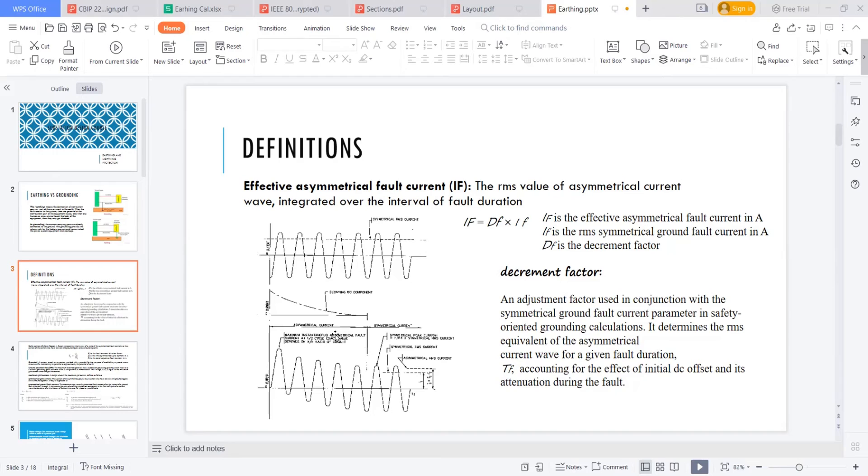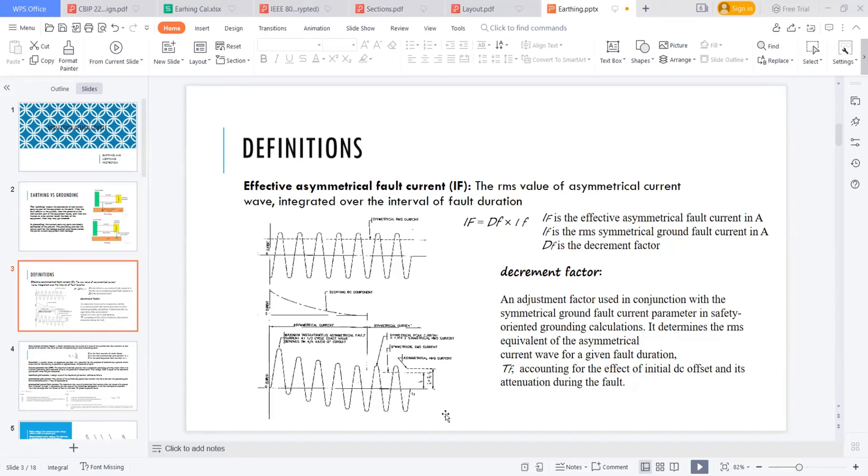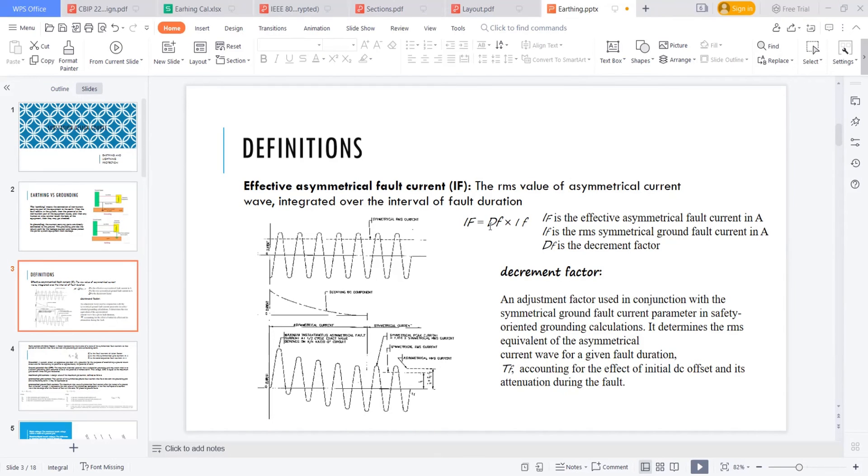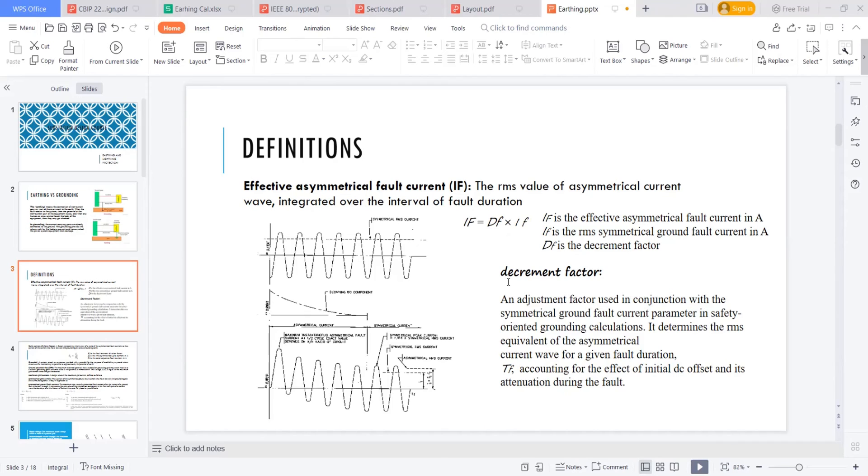This is the asymmetrical fault current. And after the decaying of this DC component, the fault current will come to its normal position where this symmetrical current is not having the DC component, where the asymmetrical current is having the DC component. Now the question is, what is this asymmetrical current? This asymmetrical current can be calculated by using some decrement factor into the symmetrical ground fault current. This is a decrement factor or a kind of adjustment factor, which is between the asymmetrical current and the symmetrical current. How to know this decrement factor, we will discuss that in the next few slides.